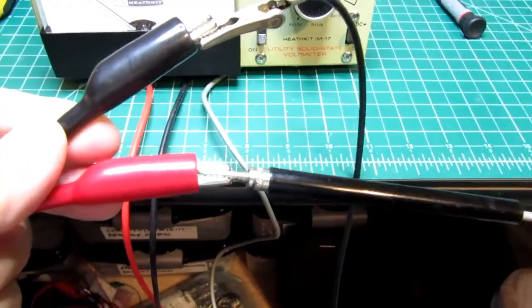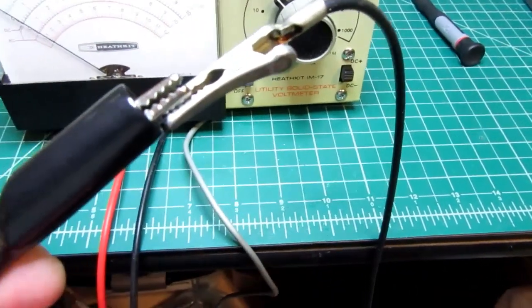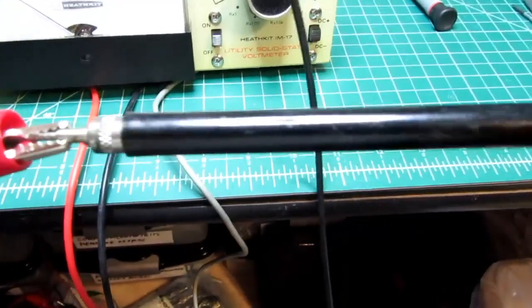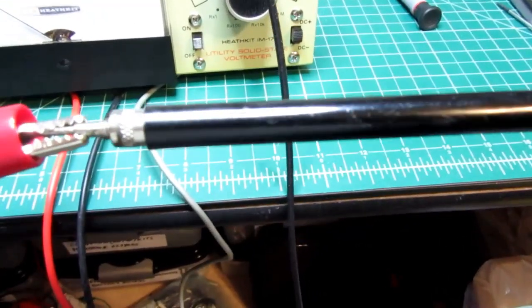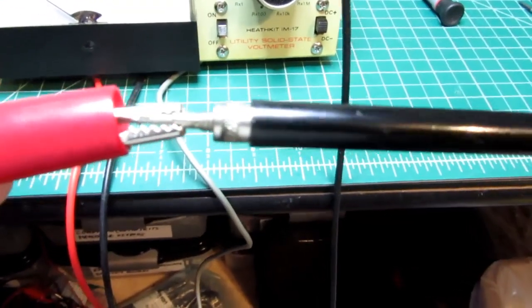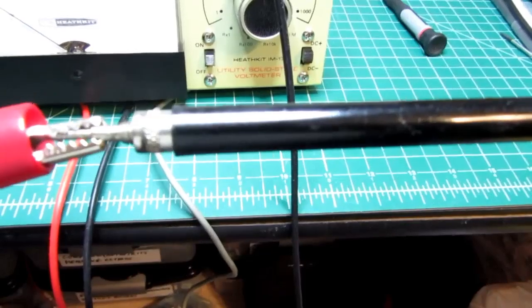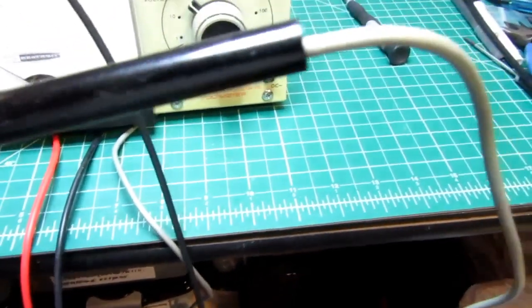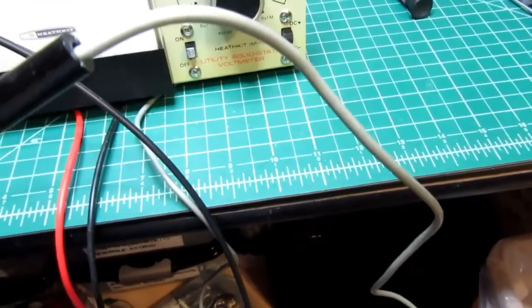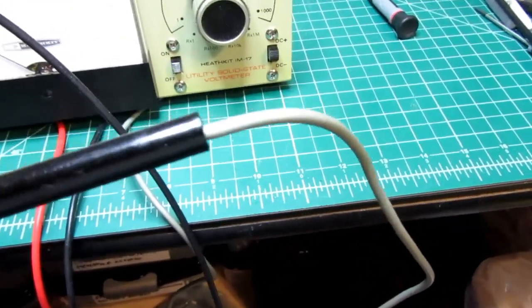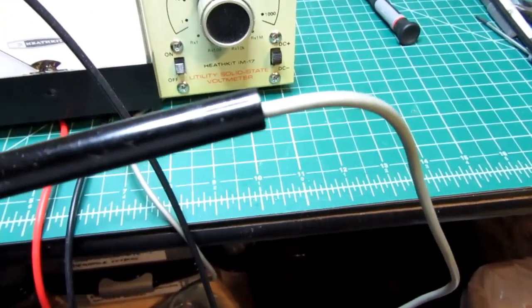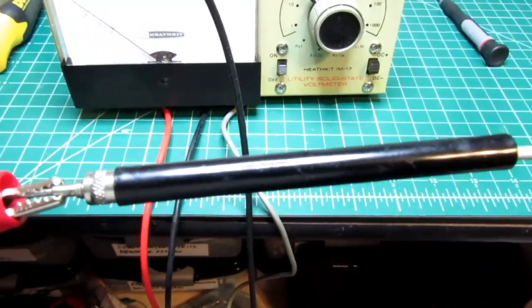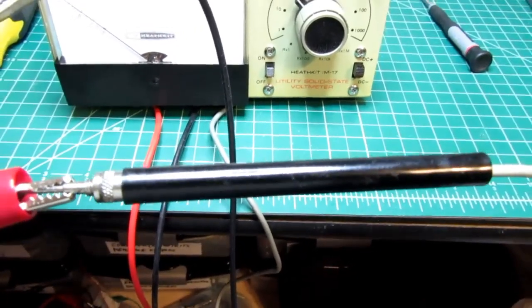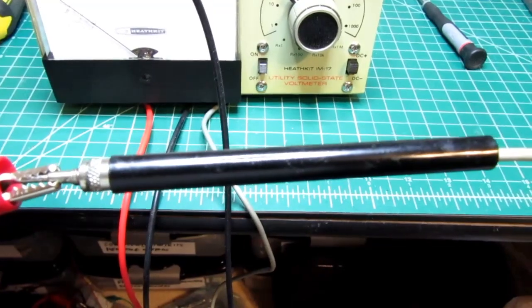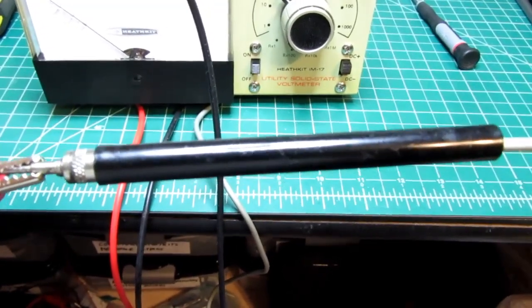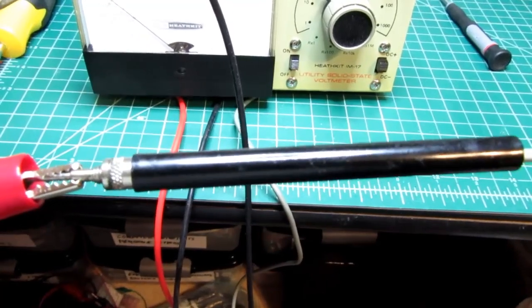And I should mention that for this, I'm using the black alligator clip to the negative of my power supply, and the black test probe on the meter to the positive side of the power supply. This is the probe that has a 1 mega ohm resistor inside of it. It also has a shielded cable, even though it looks like just a gray insulated wire. It's actually a shielded cable, but the shield is not terminated at this end. There's nowhere to terminate it to. The DC volts function is the only instance on this meter where the black probe gets used. Otherwise the red probe gets used for everything.